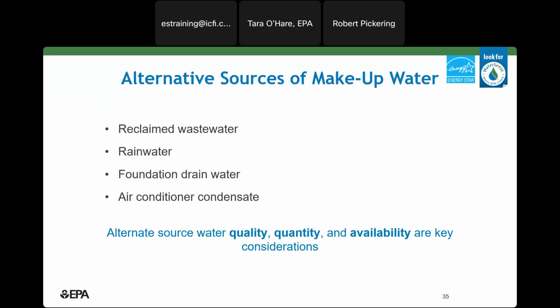So another opportunity to reduce the amount of potable water used in a cooling tower is to identify an alternative source of water that could be used to supplement or fully replace city water in the makeup line. Some possible sources of makeup water include reclaimed wastewater that's often provided by your local municipality, rainwater, foundation drain water, and air conditioner condensate. One thing to remember when assessing alternative water sources is that the water quality, quantity, and availability should be considered. So only use alternative sources when you're able to match the quality of the alternative source to the needs of the system.